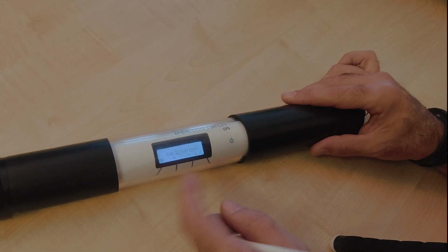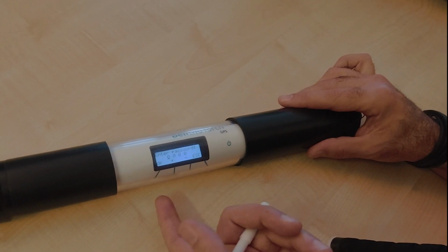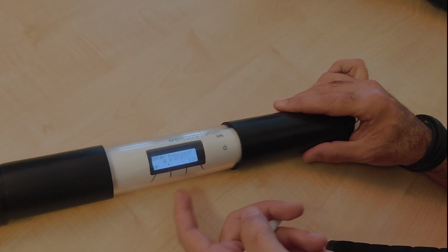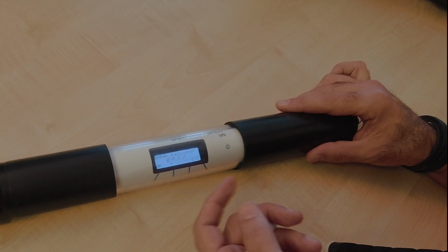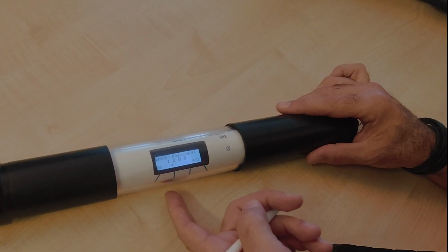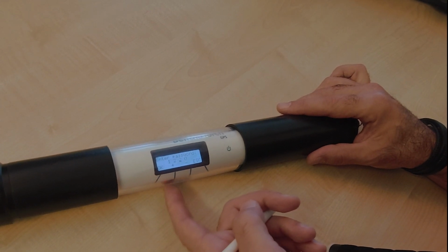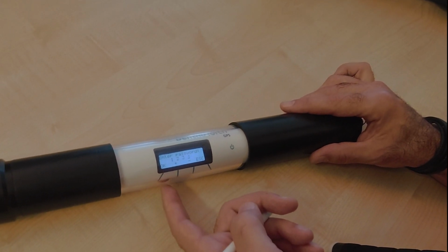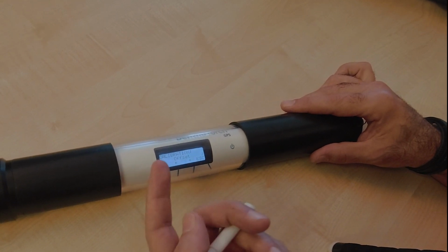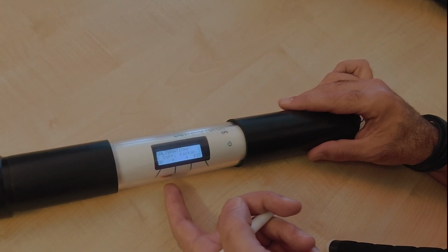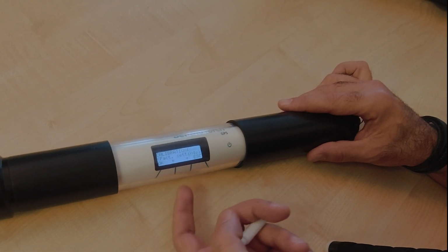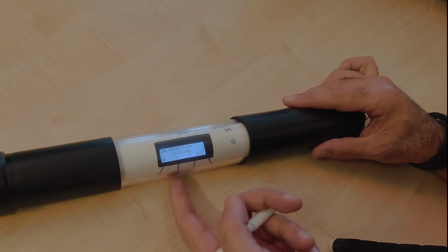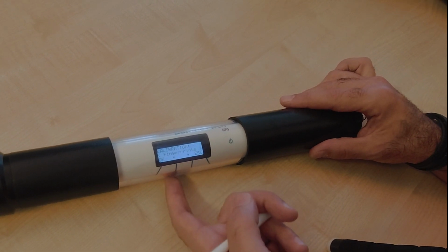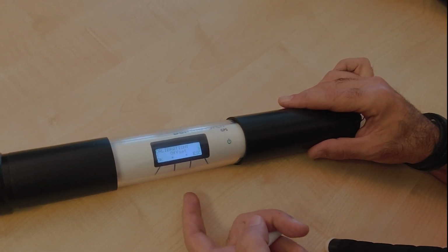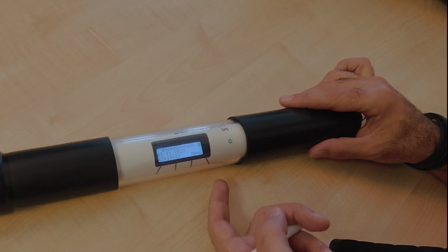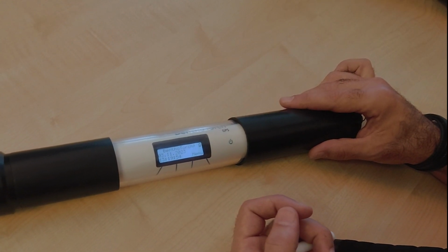And also we have a calibration menu. The calibration menu needs a password, because we recommend that untrained people do not use this, but of course everything is mentioned in the manual on how you can do this. The password is 1234. You can calibrate the offset, you can put in correction factors, or you can return the unit to the factory setting. You can check the voltage or calibrate the fingerprints of the unit, and also do background calibration. These are all from the BenthoTorch menu that I can tell you.